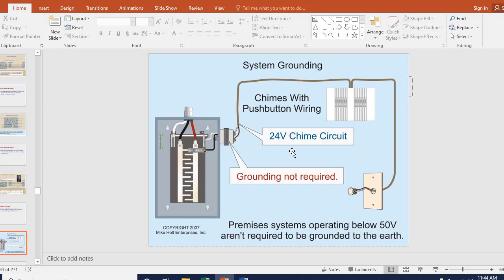Right here it's saying grounding is not... I never thought about that, but that's a doorbell. That's a simple little old doorbell system. There's your chimes, and there is your push button at your door. The grounding is not required because it's operating below 50 volts. Now, what happens if you get a lightning strike? I don't know. I guess you'll be replacing the doorbell transformer. That's 120 volt to 24 volt. It'll probably take out your chimes or your push button, but it doesn't require ground.